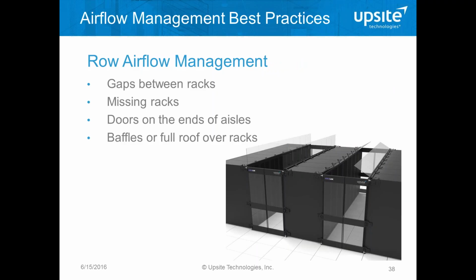Then after the raised floor and the rack are managed, we're moving on to the row airflow management. There's a number of gaps here that need to be addressed, the gaps between cabinets, even if those are just an inch or two apart. And then, of course, we start to see problems where there's missing cabinets, either from just migration of equipment coming in and out of the room, or perhaps there's a building column in place preventing a full row of cabinets.